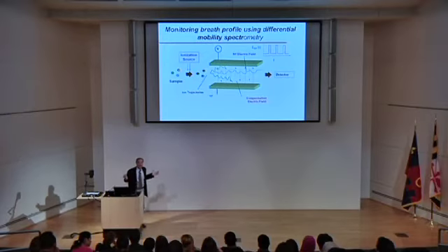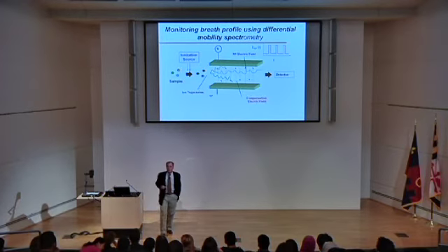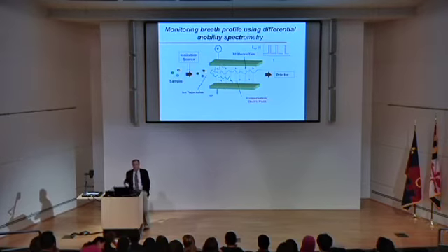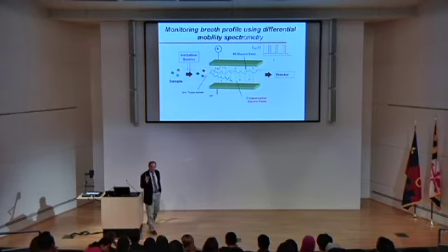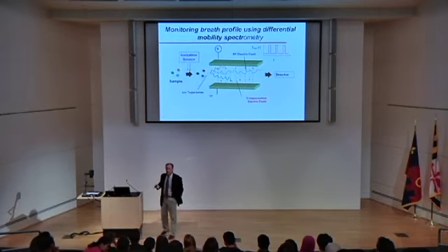This is the technique of differential mobility spectrometry. You have a radio frequency field, and then you have plates, and only certain ions get to the detector. It's essentially like a normal quadrupole mass spectrometer, except it's based on ion mobility in the electric field. It's very small, very simple, and the actual nuts and bolts of the instrument is only 4 centimeters squared.